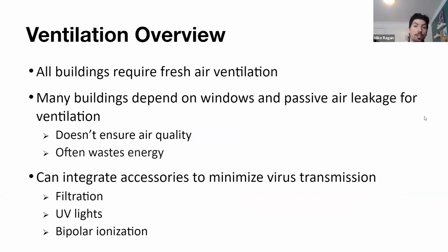Now, when it comes to ventilation, we need to remember that all buildings require fresh air ventilation, especially if we're talking about the commercial end of the spectrum. Many buildings depend on windows or just standard passive air leakage to handle their full ventilation loads. This is not an efficient way of delivering ventilation to a space. It's passive, and it doesn't ensure air quality. There's no metric for CO2 levels to deliver that fresh air. And there's ultimately no guarantee you're going to have a well-distributed fresh air load throughout a space if you're just depending on windows. The central zones of the building aren't so lucky to have the windows that are on the perimeter spaces.